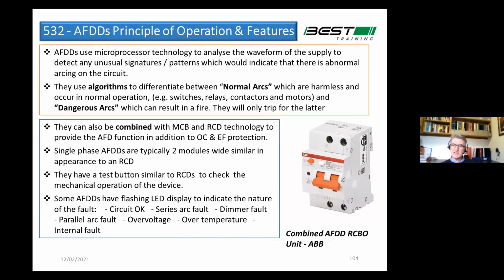So there are single module versions out there, but you can see there are 2 buttons on it, orange and white. The orange button there is the test button for the arc fault function. The white button is the earth leakage function. And to the best of my knowledge, when it trips out, the little LED here is a phase change LED, so it'll tell you whether it's an arc fault or an earth leakage fault. And if it's neither of those, then it's an overcurrent. So, a very clever piece of technology. Different manufacturers have different ones out there, and I need to do a little bit more research on it myself. I'd love to get some hands-on time, play around with them and see what they look like. So that's what they do.